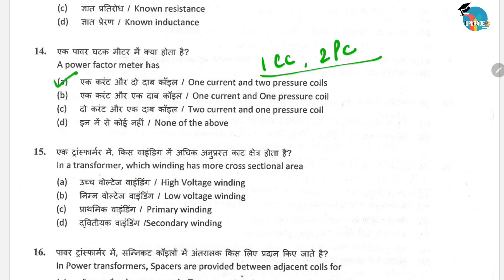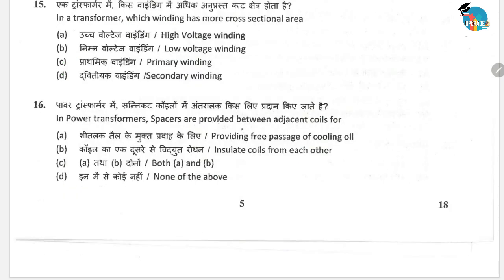Next is in a transformer which winding has more cross sectional area. So in a transformer, the low voltage winding will have more cross sectional area. Moving on to the next question, in a power transformer spacers are provided between adjacent coils for. So the spacers are provided between the adjacent coils for providing free passage for the cooling oil and to insulate the coils from each other. So the correct option is option C, that is both the above options are correct.